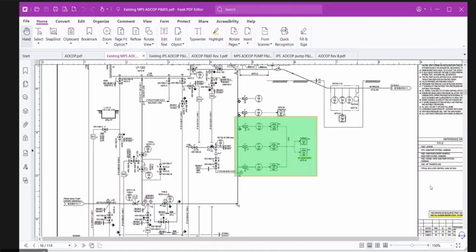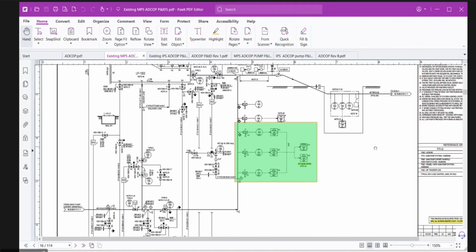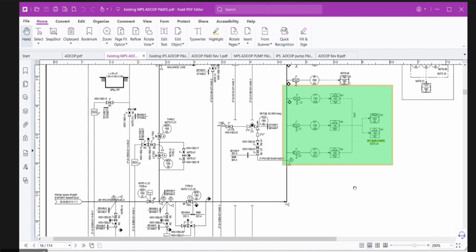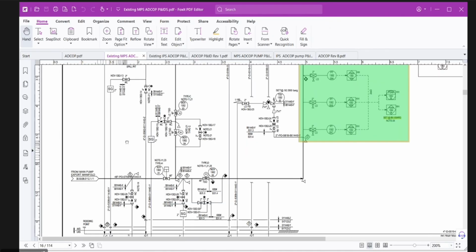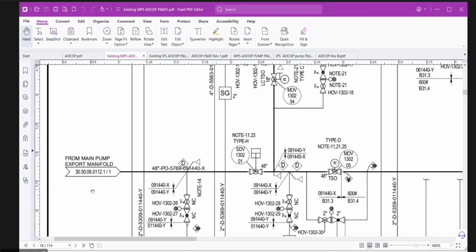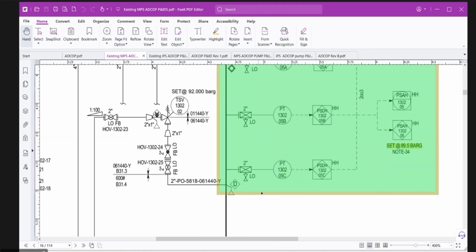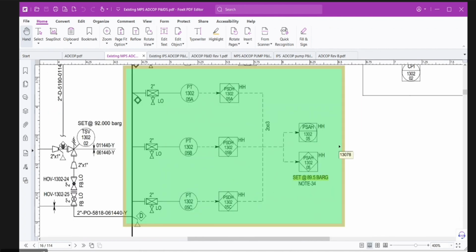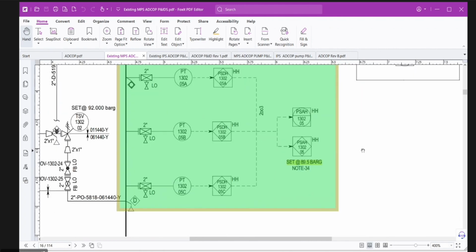So guys, as per the current discussion, if 70% flow is creating ESD2, and if high pressure happens, ESD2 means they will cut off all the power supply. Yes, all the power supply. In that case, that may be different than this pump. Then this is independent. Yes, independent. This is coming from the existing header of the MPS. We have here in the header the charge voting high pressure 2 out of 3.